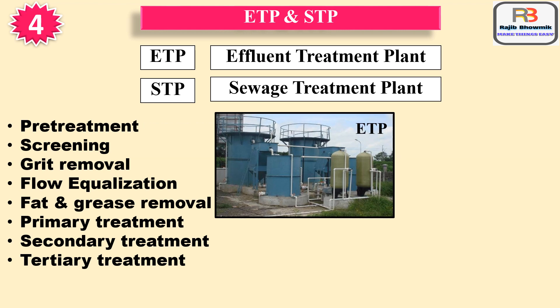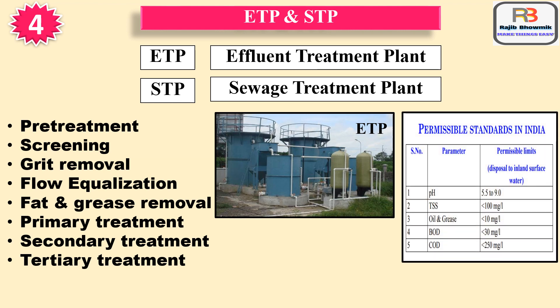Treated water should meet all parameters as prescribed by the Pollution Control Board. Chemical dosing is done in ETP and STP to get desired parameters in the outlet effluent. Permissible standards in India: pH 5.5 to 9, TSS (total suspended solids) less than 100 mg/litre, oil and grease less than 10 mg/litre, BOD (biochemical oxygen demand) less than 30 mg/litre, and COD (chemical oxygen demand) less than 250 mg/litre.